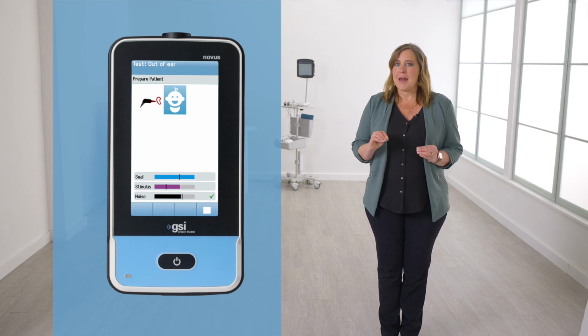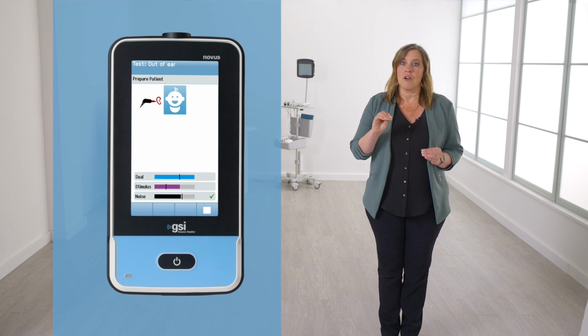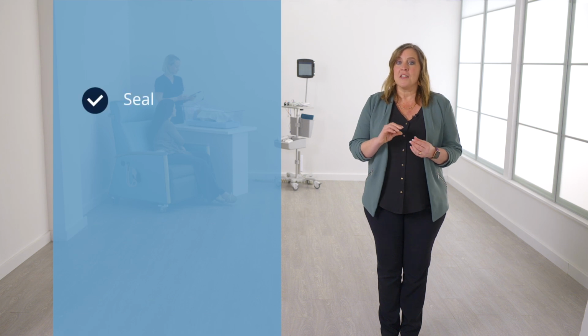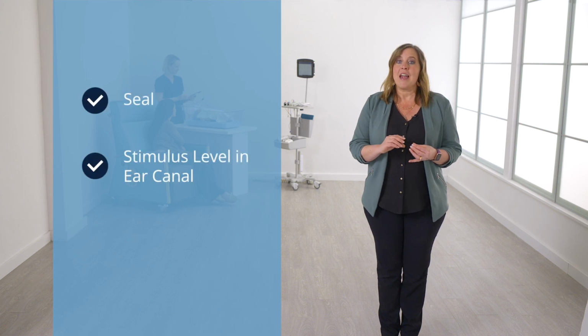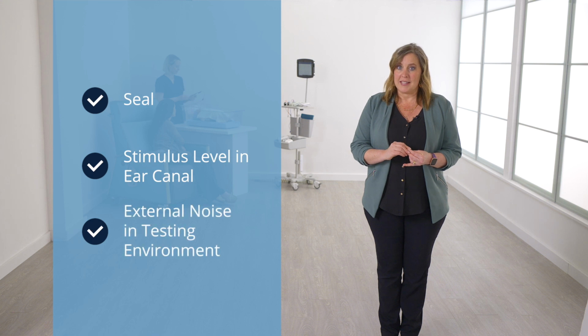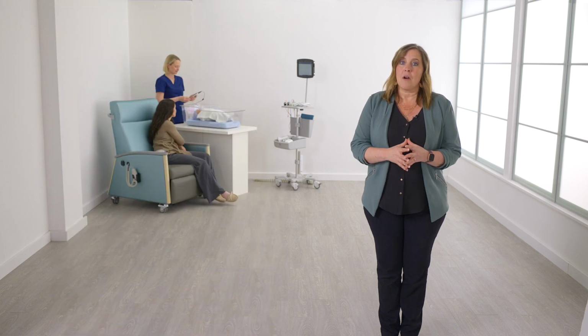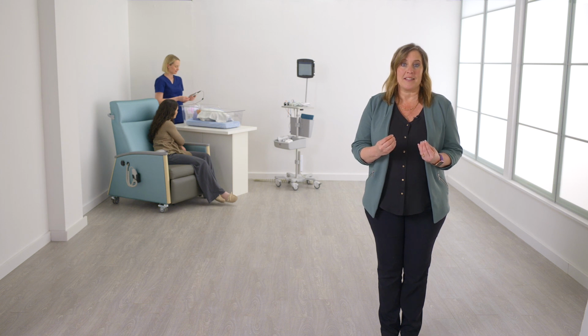This step automatically evaluates the quality of the probe fit in the ear canal to ensure a quality fit and therefore a reliable test. The probe check verifies the seal, the stimulus level in the ear canal, and the external noise in the testing environment. A check mark for each parameter indicates that the fit quality is acceptable for testing.